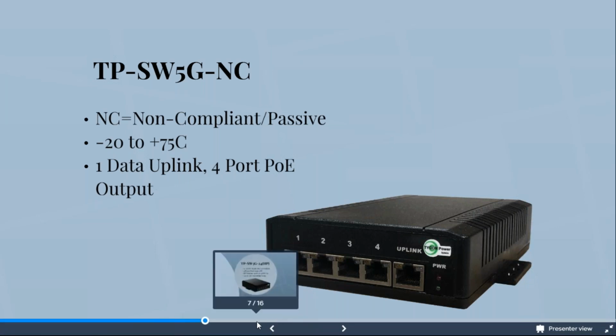Absolutely. Because, like I said, most manufacturers have different power requirements. The longer I've been doing this, I do a lot of system designs for tower sites to power off of solar or as battery backup, and there are really no two designs the same. Customers will come to us and say, well, I've got this access point, and I read data sheets all day long. It's super exciting. Sarcasm intended. And so we'll see a data sheet. It'll say, okay, this is 24-volt passive.